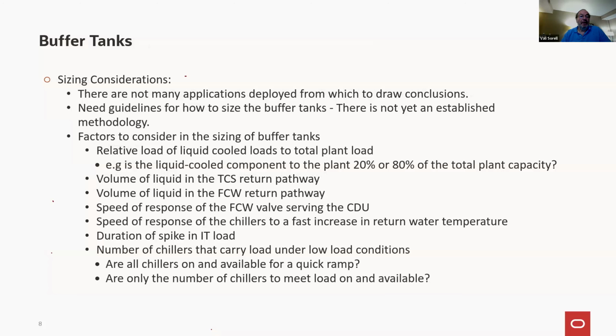So I see that Shlomo, hey Shlomo, asks about 2-phase. If you're talking closed loop 2-phase, no, we haven't looked at it. I know there are opportunities out there, but right now we are not really dealing with that. At some point in the future, we may, and we'll have to revisit these buffering conditions and load issues carefully at that point. It does change the infrastructure tremendously, because if you have 2-phase, you're no longer talking about propylene glycol. You're talking about a refrigerant of some type.